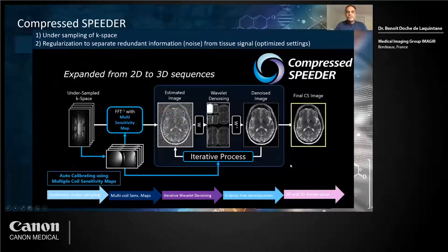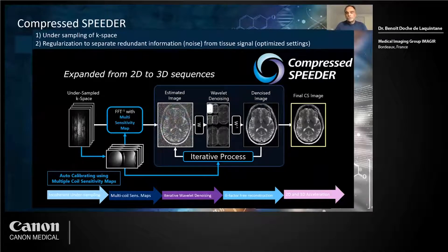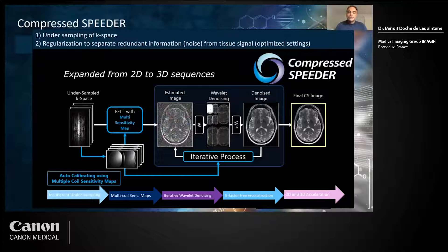The additional technique I use is compressed SPEEDER. It is based on an undersampling of k-space and there is a regularization factor to separate the redundant information — the tissue signal from the noise — and it helps to optimize the settings. It's a trade-off between cleaning the noise from the tissue signal. If the regularization factor is too high, you will miss some clinical information.